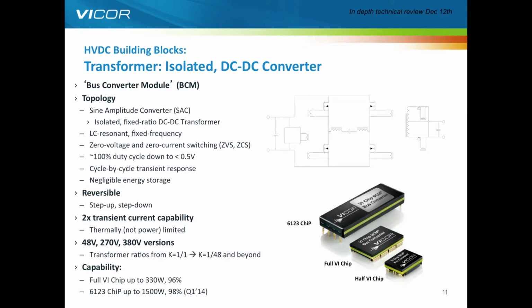A DC voltage is applied on the primary. We have a full bridge in this example, which creates a pure sine wave, which leaps across the transformer gap and then is rectified again using MOSFETs back to a DC level. So for example, if we had an input of 380 volts and a transformer ratio, a K factor of 1 divided by 8, then we go from 380 to 48 volts on the output.